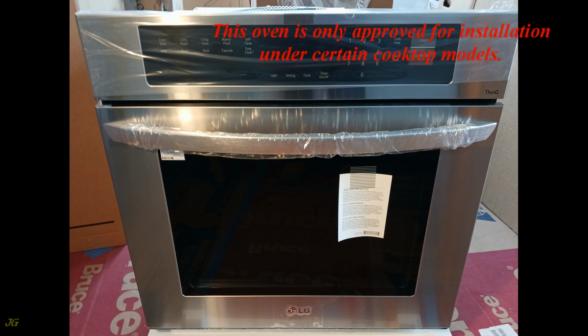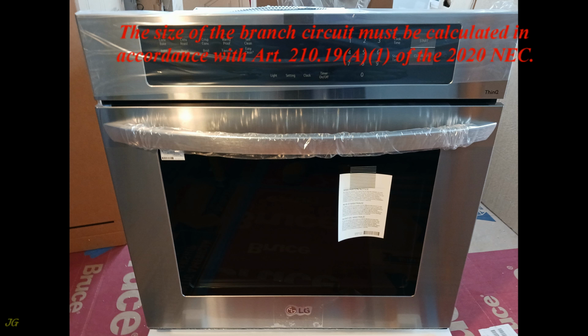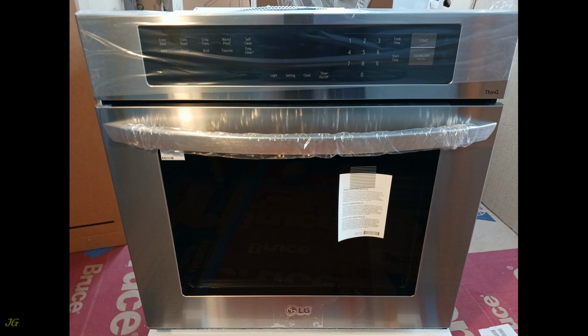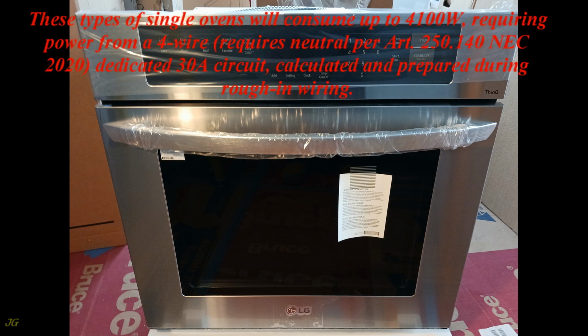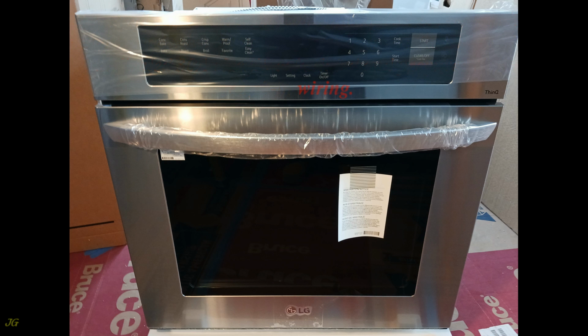This oven is only approved for installation under certain cooktop models. The size of the branch circuit must be calculated in accordance with Article 210.19 A(1) of the 2020 NEC. These types of single ovens will consume up to 4,100 watts, requiring power from a 4-wire circuit, which requires a neutral per Article 250.140 NEC 2020, a dedicated 30 amp circuit, calculated and prepared during rough-in wiring.